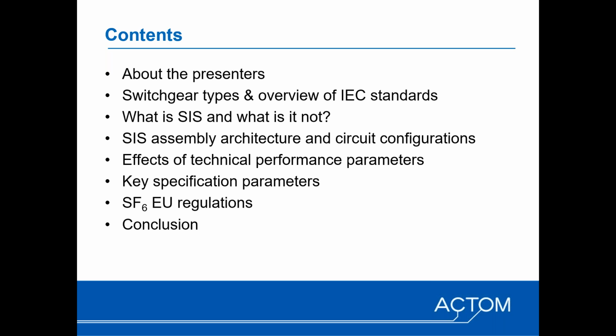Then Johanna is going to take us through some slides on the effects of the technical performance parameters and important issues to consider in the design of solid dielectric insulated switchgear, or SIS. We're going to look at key specification parameters and then briefly cover the relevant issue of the latest EU regulations on fluorinated gases, and specifically SF6, and then hopefully draw some conclusions.